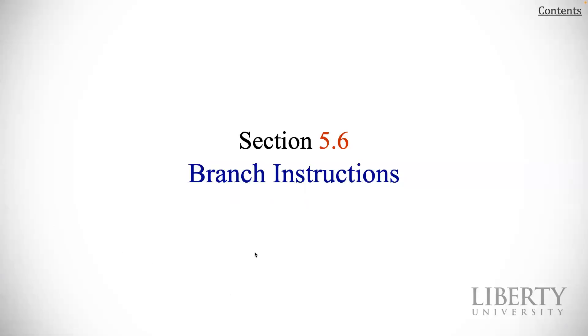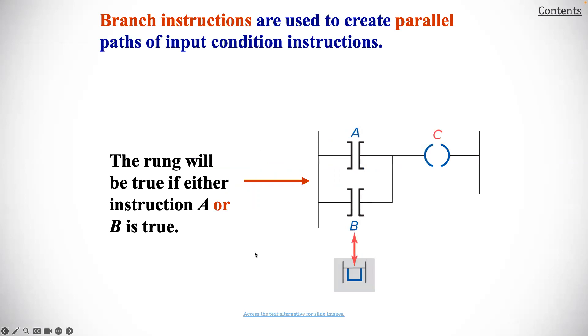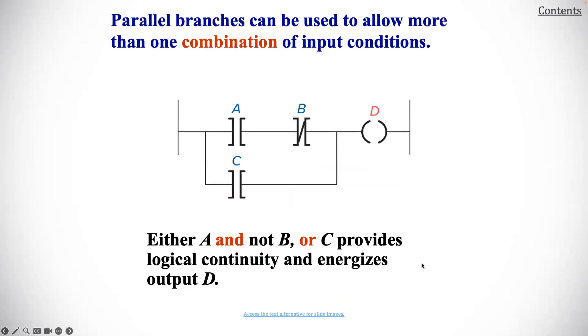Let's get into branch instructions. Branch instructions are used to create parallel paths of input condition instructions. A rung will be true if either instruction A or B is true. Parallel branches can be used to allow more than one combination of input conditions — either A and not B, or C provides logical continuity and energizes output D.